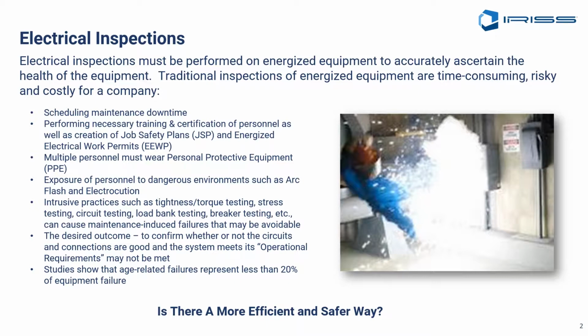You have to schedule downtime with your maintenance personnel in order to perform a lot of de-energized maintenance tasks. And you have to train your people on how to do it safely. You may require job safety plans to be thoroughly vetted and written out so that you understand the risks involved in any given task. And you may also have to pull energized electrical work permits if you're going to do this work open panel and energized. And of course, your personnel have to be wearing PPE. They have to have the right level of arc flash incident energy protection type of equipment available and be wearing it when they're performing these tasks.